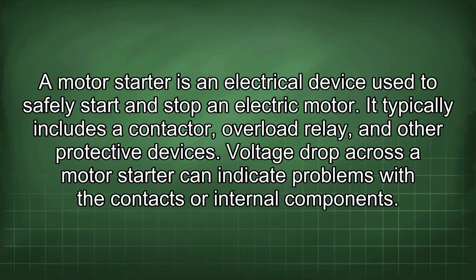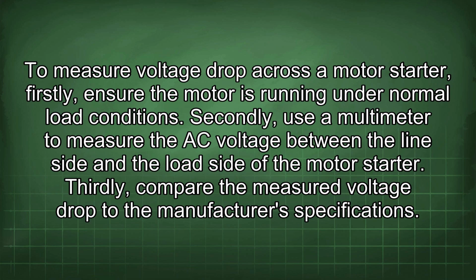It typically includes a contactor, overload relay, and other protective devices. Voltage drop across a motor starter can indicate problems with the contacts or internal components. To measure voltage drop across a motor starter, firstly ensure the motor is running under normal load conditions. Secondly, use a multimeter to measure the AC voltage between the line side and the load side of the motor starter. Thirdly, compare the measured voltage drop to the manufacturer's specifications.